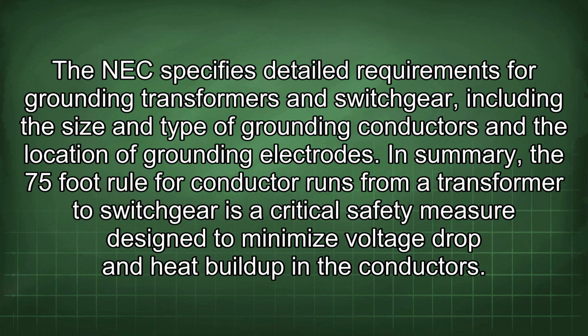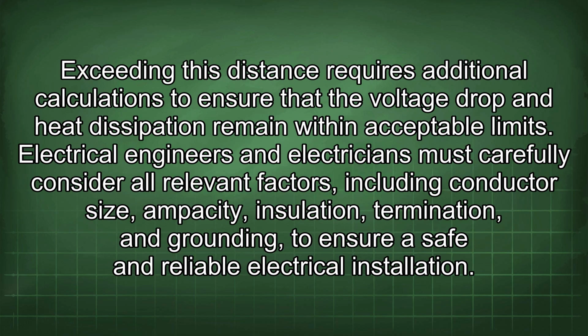The NEC specifies detailed requirements for grounding transformers and switchgear, including the size and type of grounding conductors and the location of grounding electrodes. In summary, the 75-foot rule for conductor runs from a transformer to switchgear is a critical safety measure designed to minimize voltage drop and heat buildup in the conductors. Exceeding this distance requires additional calculations to ensure that the voltage drop and heat dissipation remain within acceptable limits.